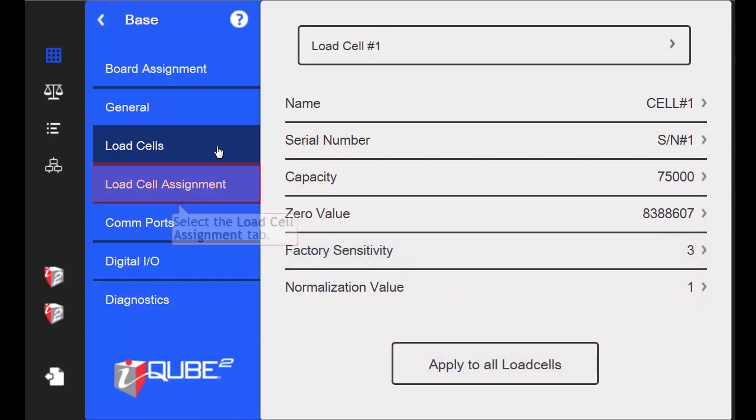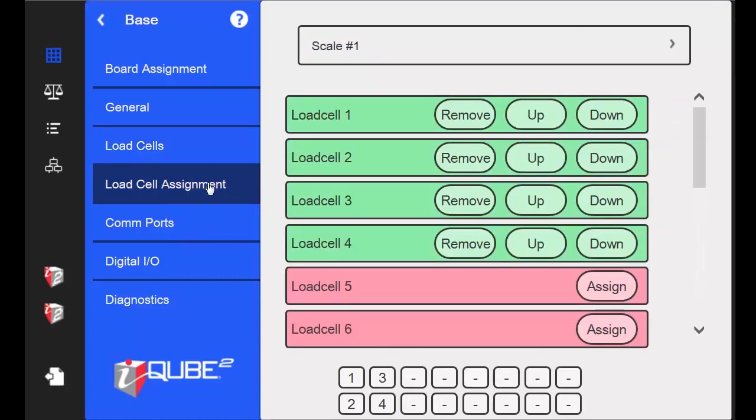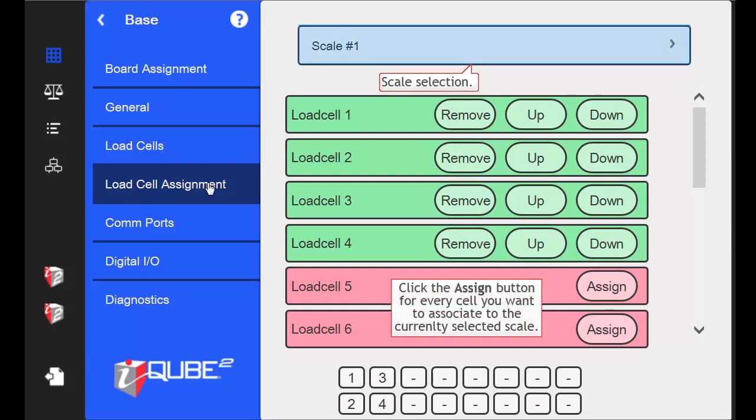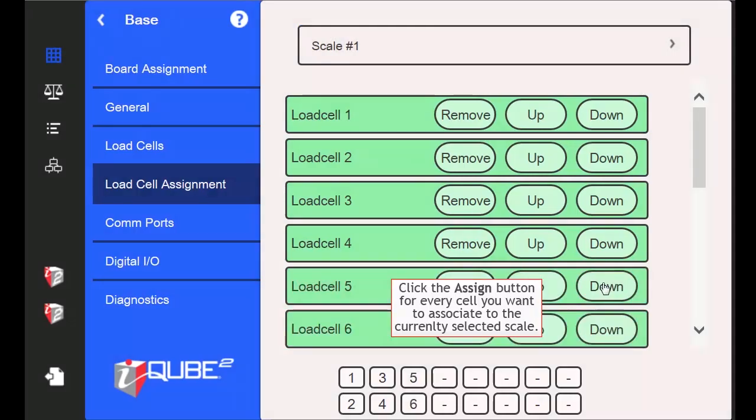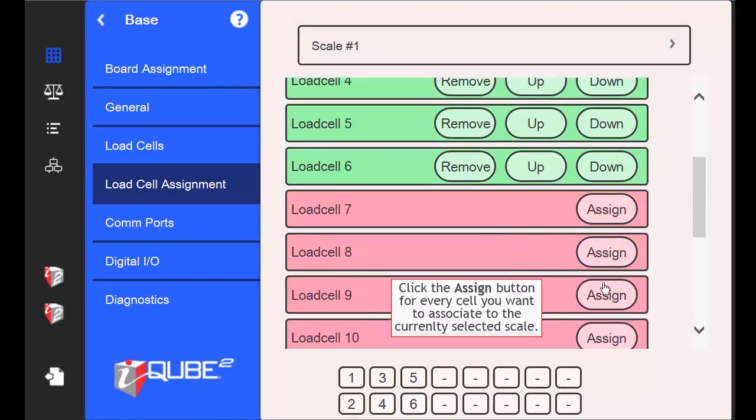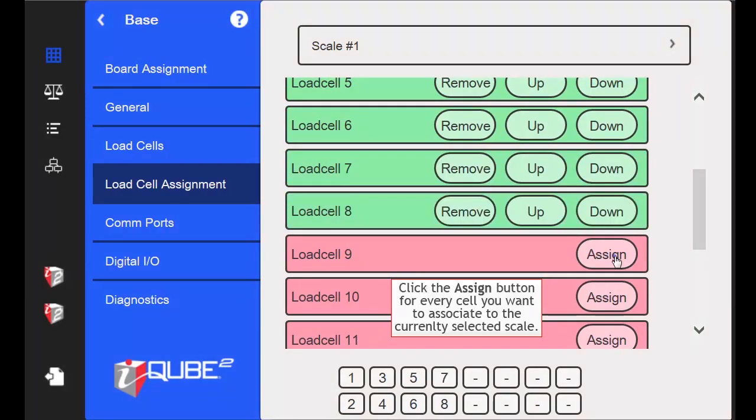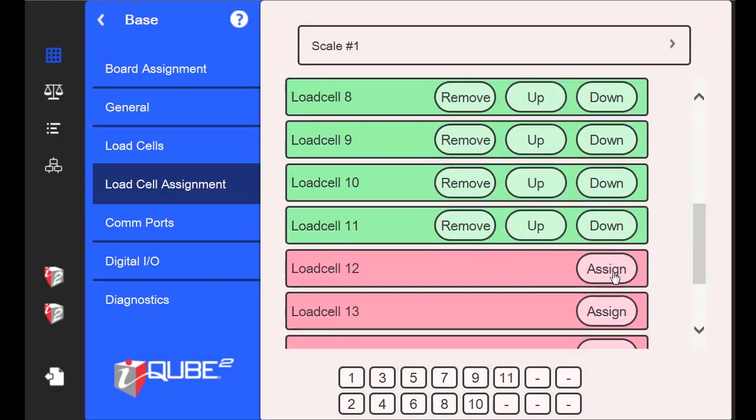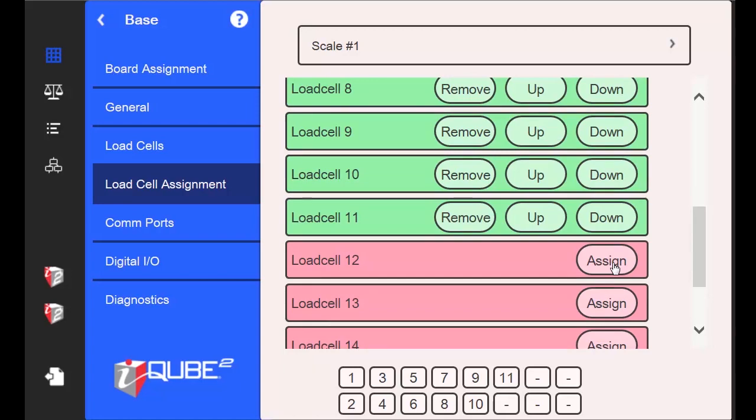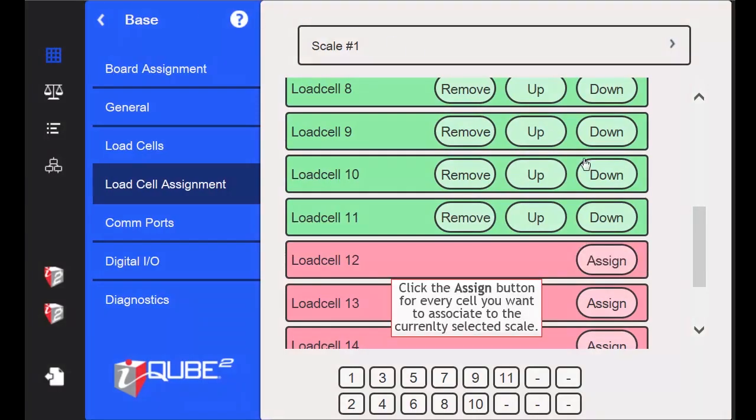I will proceed to the Load Cell Assignment tab next. You can have up to four individual scales in an iQube 2 with an option for a total scale as well. I only have one scale, so I will leave scale number 1 selected. I am going to assign an additional 8 cells to my scale for a total of 12. I will click the Assign button for Load Cells 5 through 12.